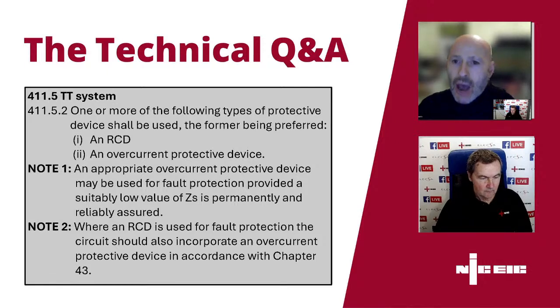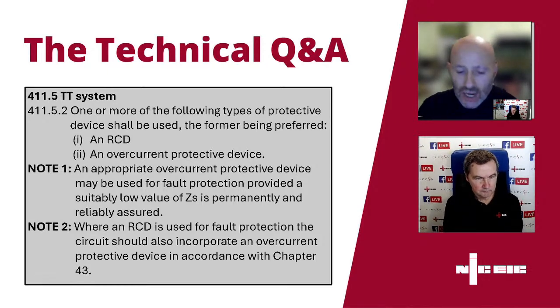Obviously, how to determine that is a different topic altogether - there's many different ways. But going back to that, yes, if you have got a low value that is permanent and assured to be reliable, the circuit breaker should be able to disconnect in the required time for electric shock protection. Yes, you can use it instead of an RCD.